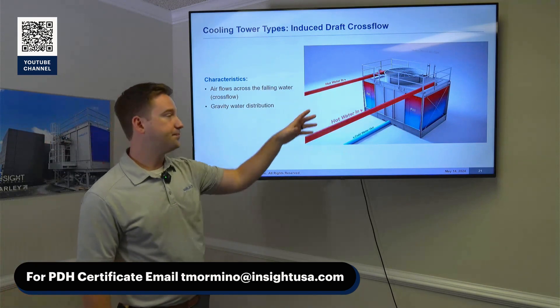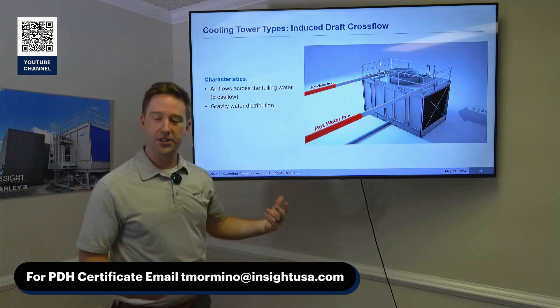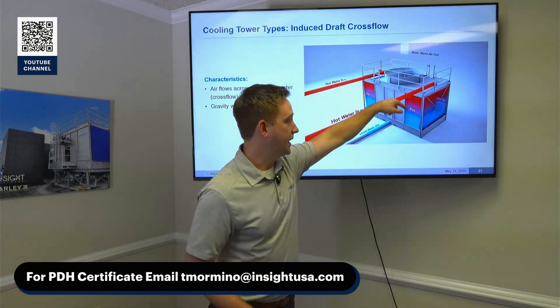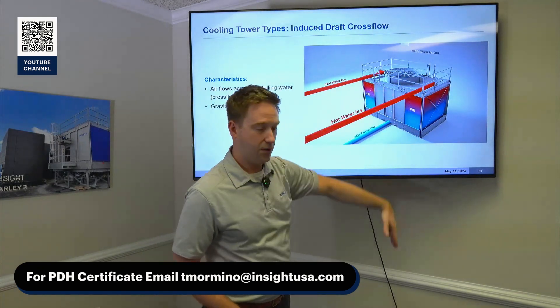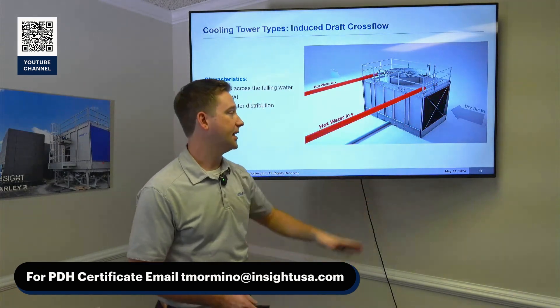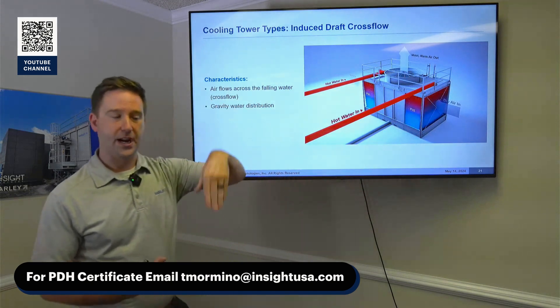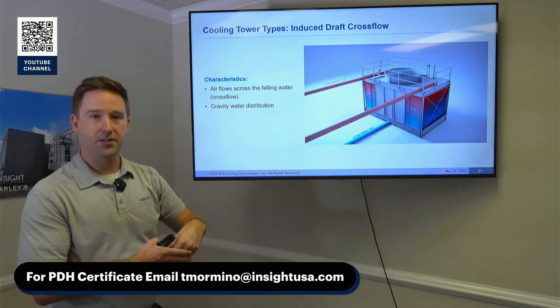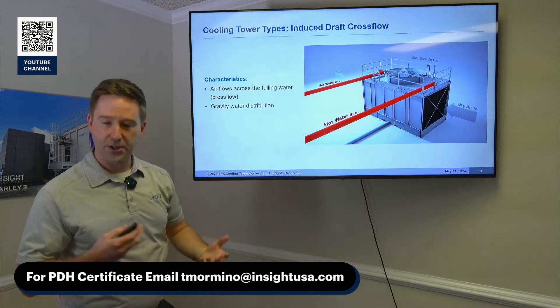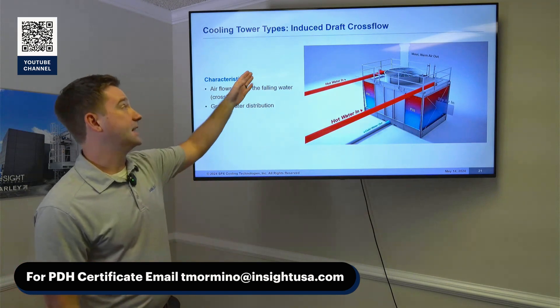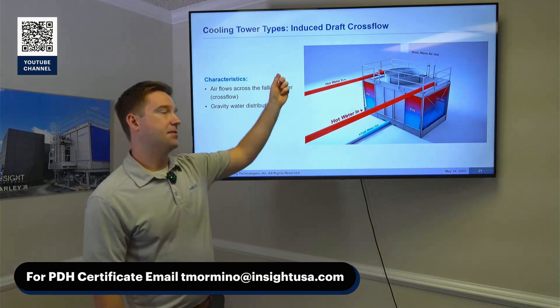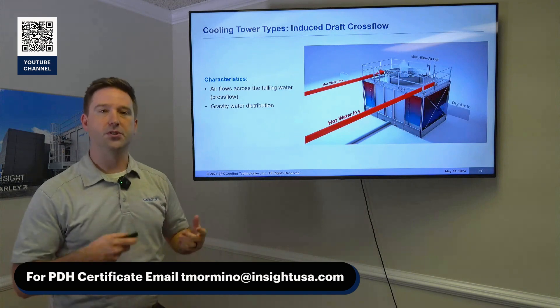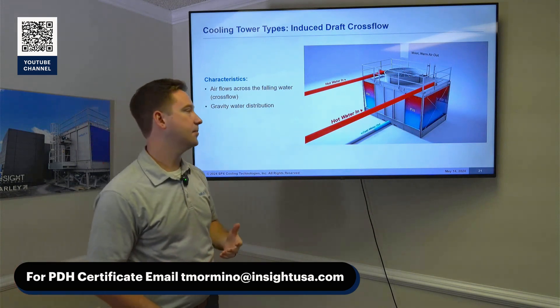This is a cross-flow tower. Water comes into the tower and goes down over the fill or heat transfer media, and air comes in from the side. The air-to-water interaction — they cross each other — that's how you know it's a cross-flow tower. It's also an induced draft, meaning there's a fan at the top pulling air through, inducing air through the tower. So it's an induced draft cross-flow tower.